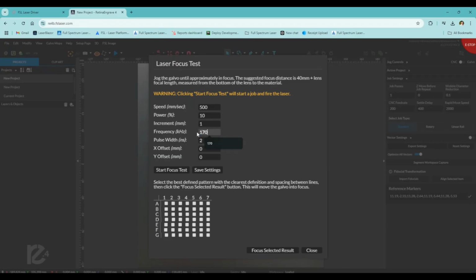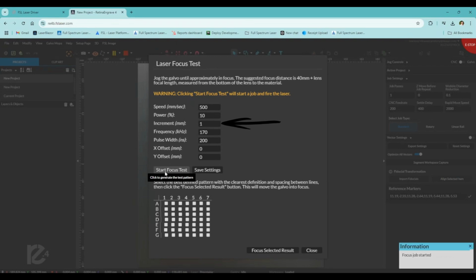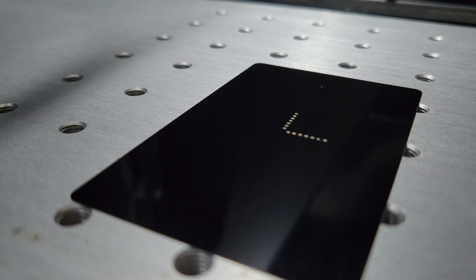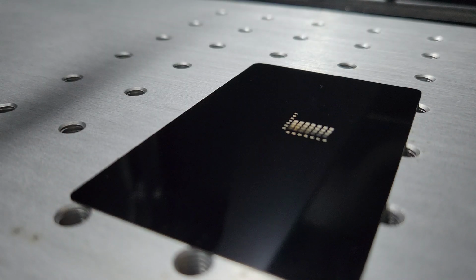I've set the increment to 1 mm, so each time the laser pulses, the head moves by 1 mm through the focal range. This test can be run multiple times, and the increment can be adjusted to a smaller value for increased accuracy if needed. Once the job starts, the laser will move upward in 1 mm increments, creating a grid-like pattern. After the job is complete, we will examine the card under a microscope to gain a clearer understanding of the results.